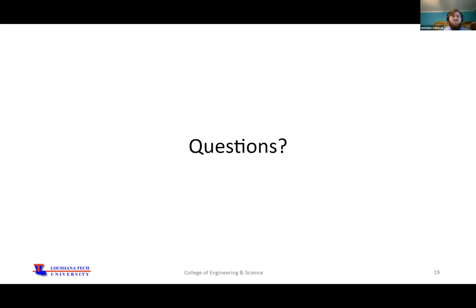No, we programmed it so it wouldn't go leading. That was the one problem we made sure it would never do, because I was pretty scared of that. The program we have in place calculates the capacitance it needs and then introduces the capacitor, and that's it. That capacitor will stay in there, so it wouldn't be hunting. I'll only introduce one stage of capacitor, and that's as close to one as we can get it. Very good, thank you.